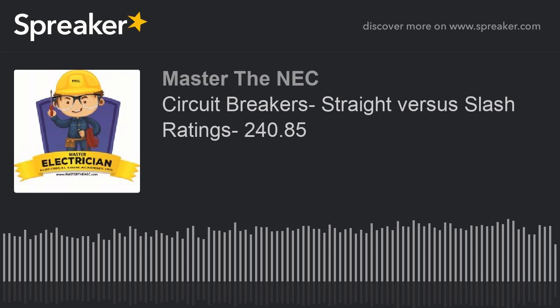Okay, all right. So that's enough of that for today. Hopefully you got that. It was a quick one, 16 minutes, 20 minutes maximum. If you have any other questions about understanding straight rated versus slash rating and the use, the key thing that I would take away is if you're dealing in an application that's straight rated, then obviously it's evaluated for a worst case scenario from phase to phase, or any of those phases to ground. So I can use a straight rated breaker in an application where it might be 120, 208, and it's a straight rated 240, then I'm okay for that application.